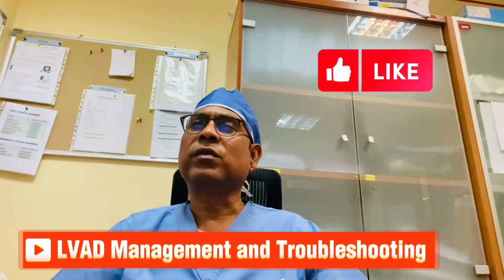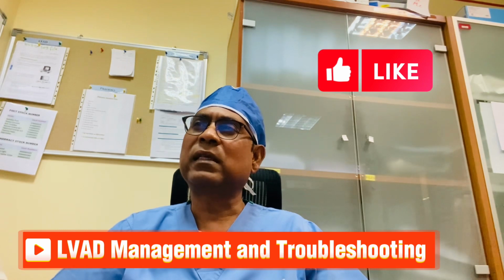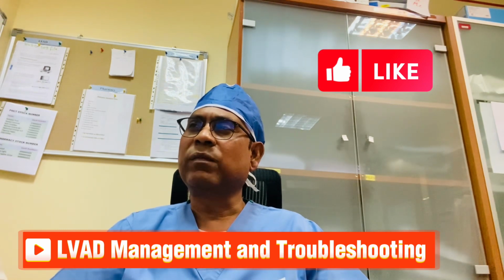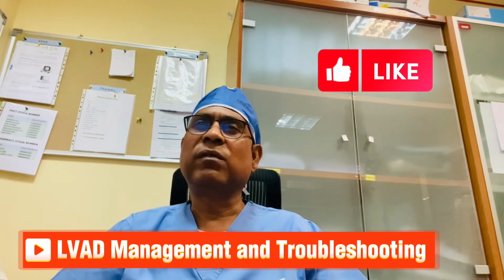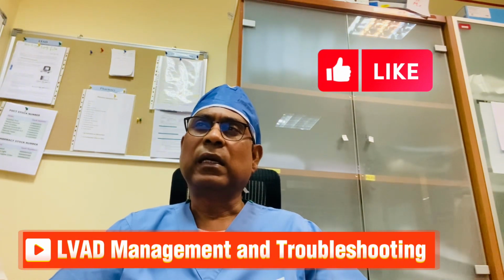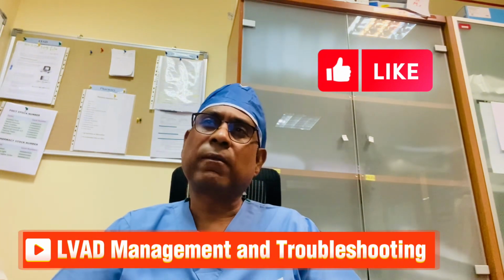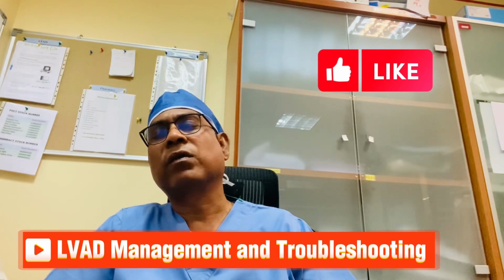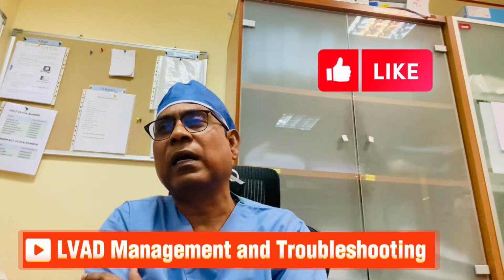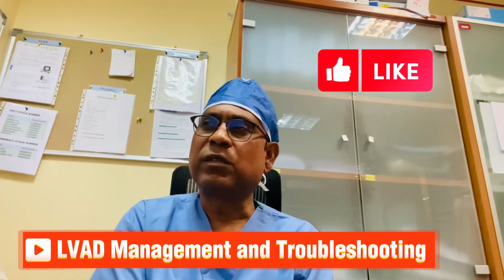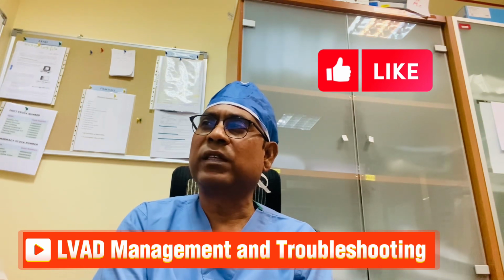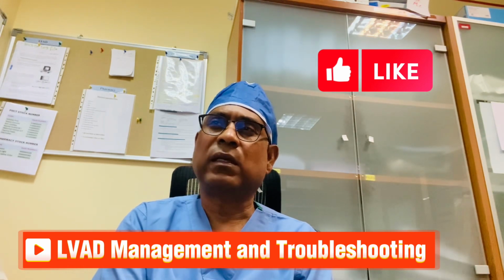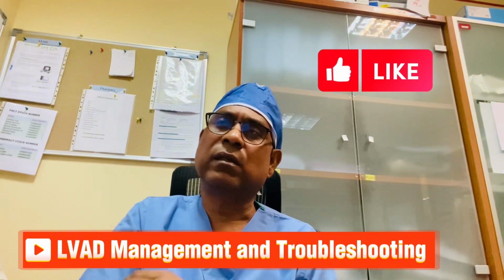Higher LV contribution to the pump flow, or less LVAD support relative to the residual LV contractility, will result in an elevated pulse index. Lower LV contractility or higher LVAD speed, meaning more LVAD support, will reduce the numerator in the formula, and the pulse index will be on the lower side.